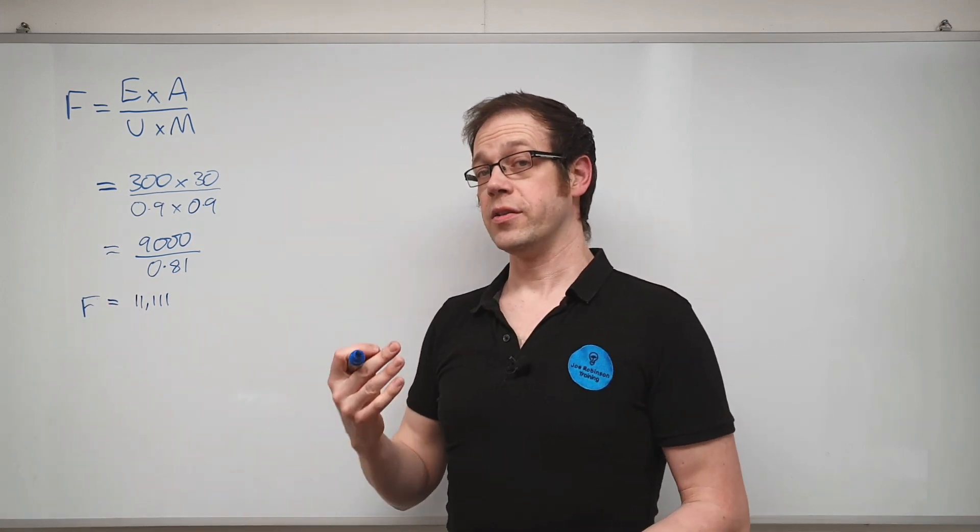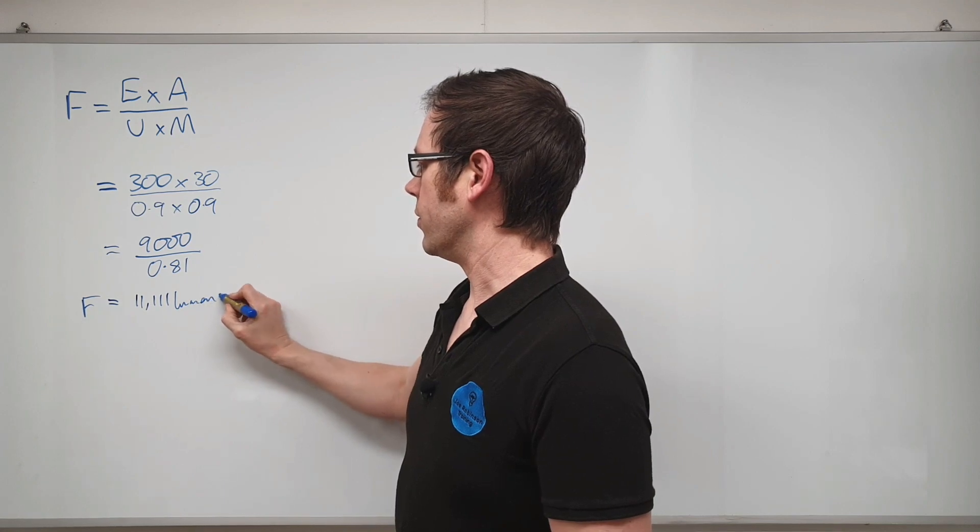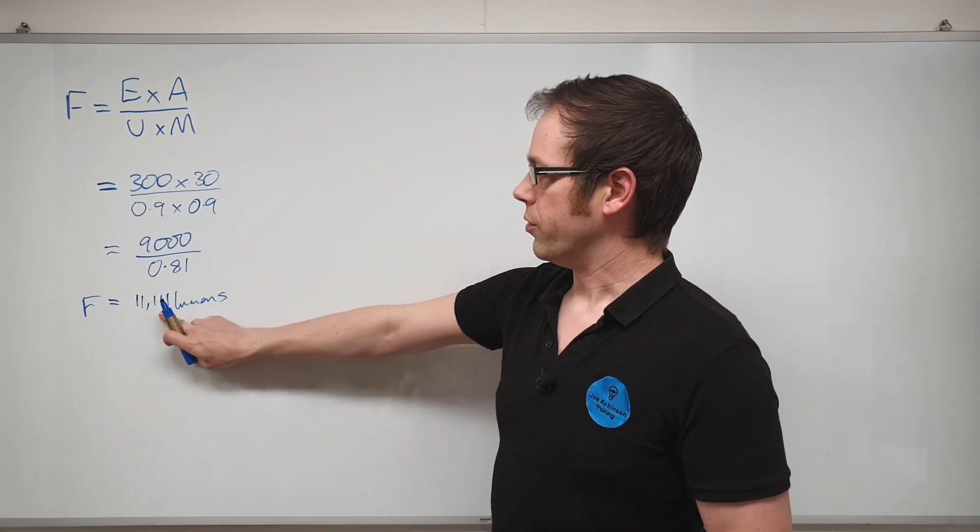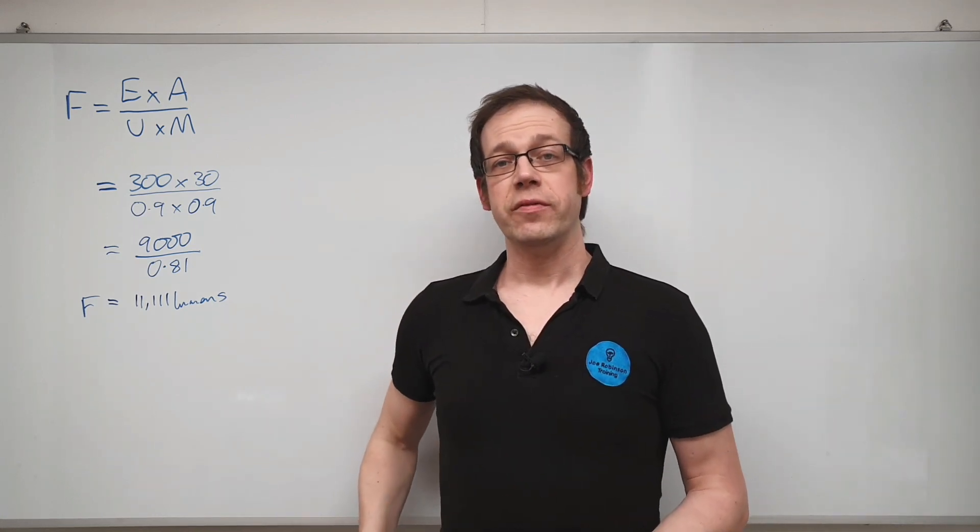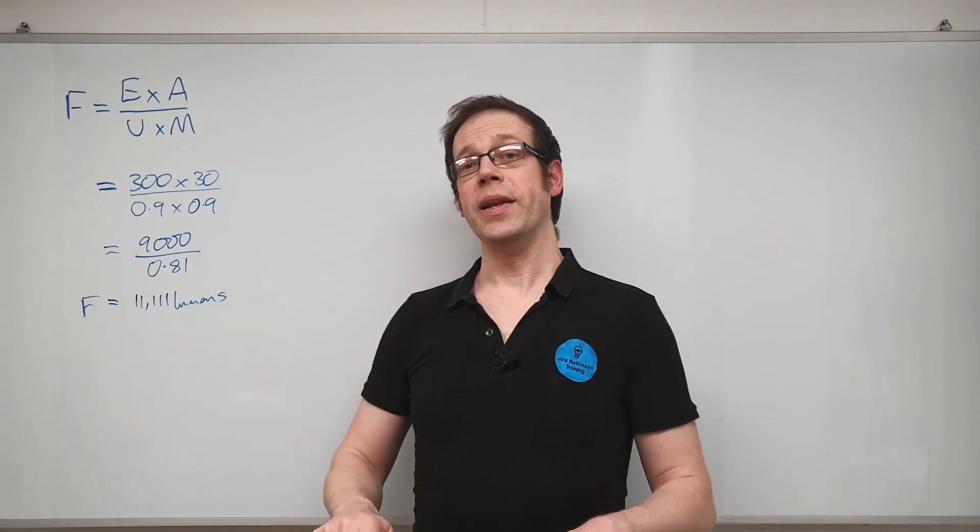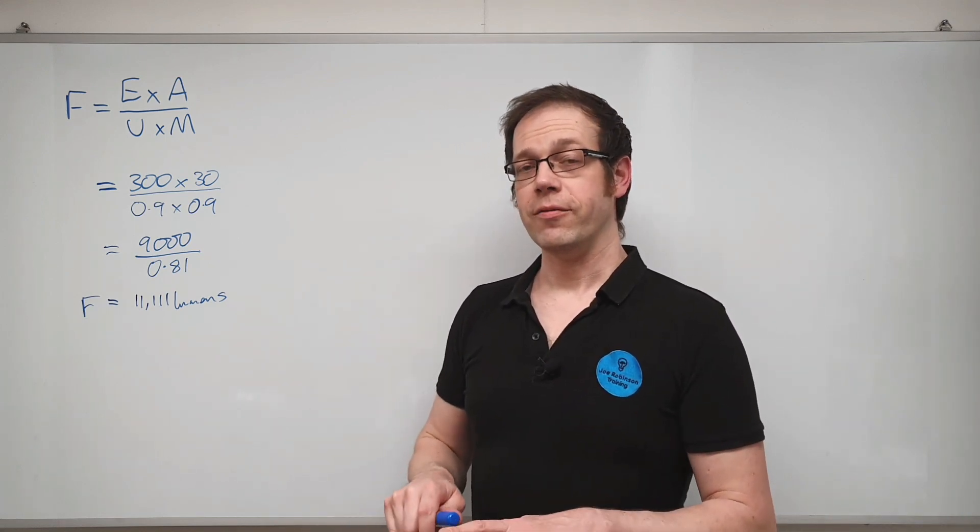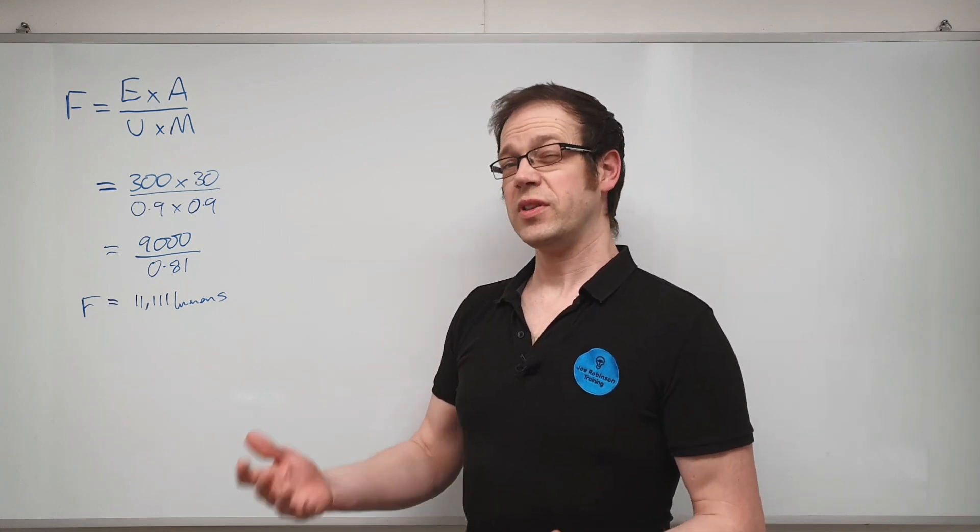Which remember is luminous flux or lumens, and is measured in lumens. So there we've got 11,111 lumens. That is the amount of light that we need our fittings in that space to give off in order to illuminate the surface to the right value of 300 lux in this case.